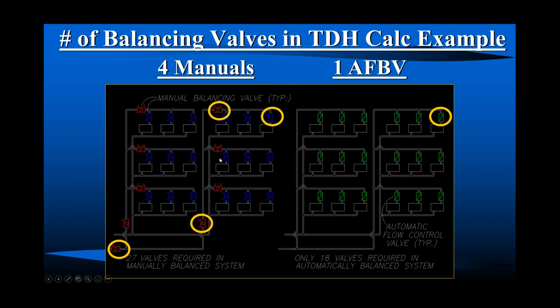We have some jobs out there, mostly, like we said here, retrofitting automatic flow balancing valves, there aren't too many jobs out there. And the ones that do occur, we're going to keep these on the terminal units, and we're going to make sure that we rebalance the risers, right? Because it's a direct return system, and we're not getting flow to that last riser. So there are some jobs out there where automatic flow balancing valves go on the risers, so at least the riser has the right amount of flow. If you need 27 GPM here, maybe that doesn't exist, but at least you have 27 here, and that pump, right? So this spring and this automatic pushes back, so 27 gets to that far riser where it did not previously.